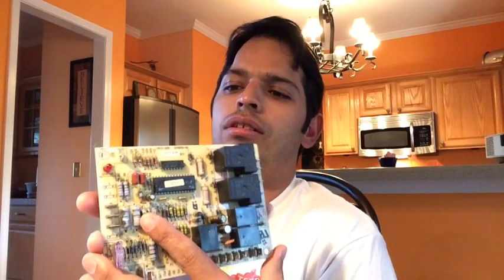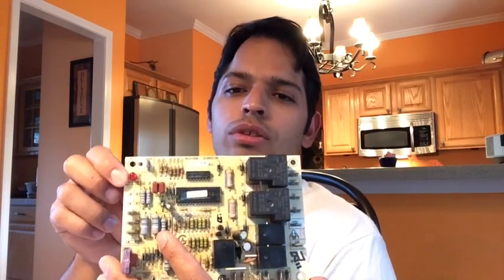Then what came up next was the inducer sensor. So we made sure that there were no clogs in that. We tested by bypassing the sensor for that, and everything worked. So the last thing that I came to the conclusion was that it was the control board. In this case, this particular unit has a B18099-06. There were no error codes. Normally they have an LED here, a red LED, that will give you some sort of error when the unit's not working properly. It was doing no such thing.